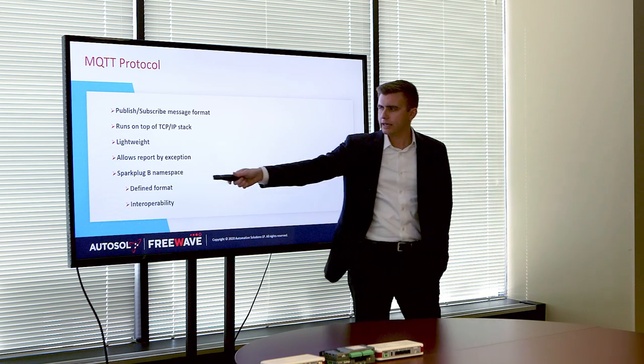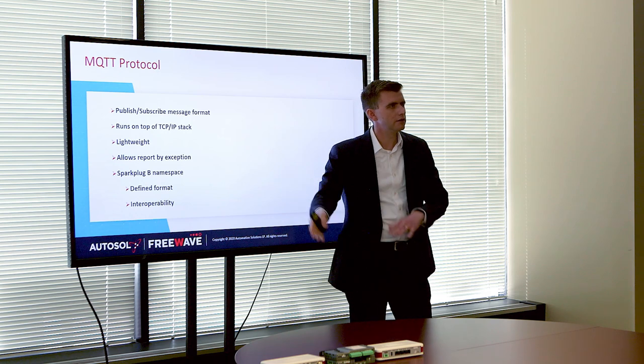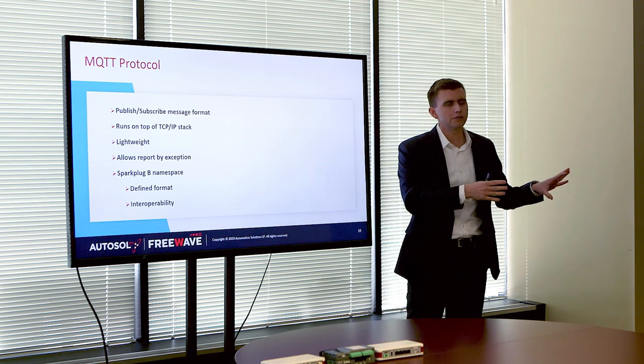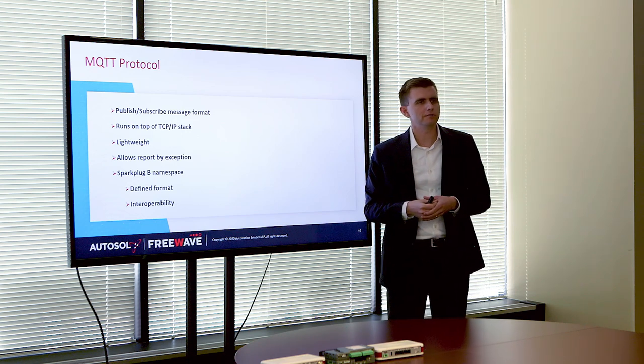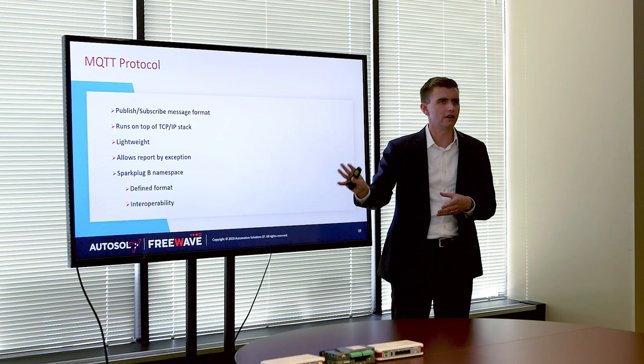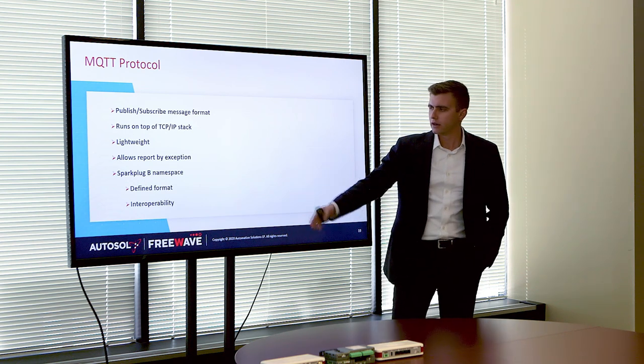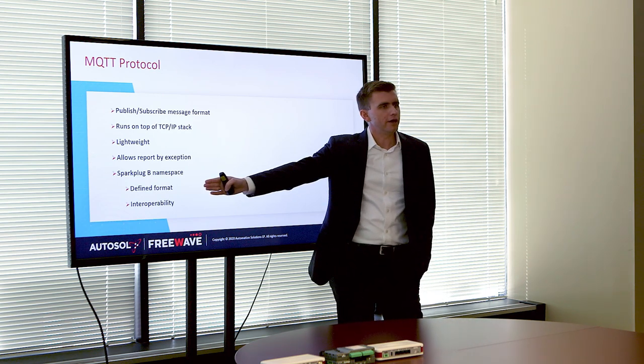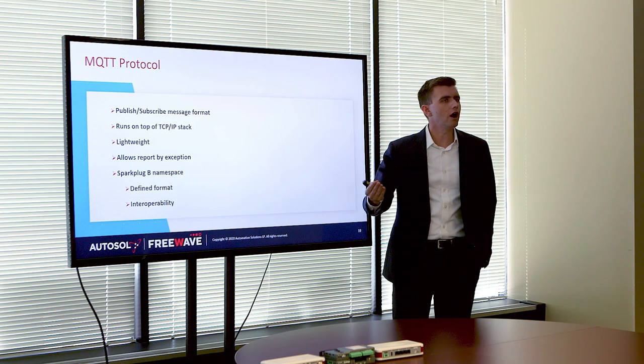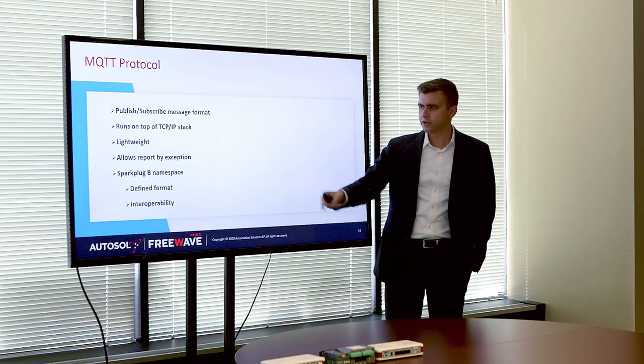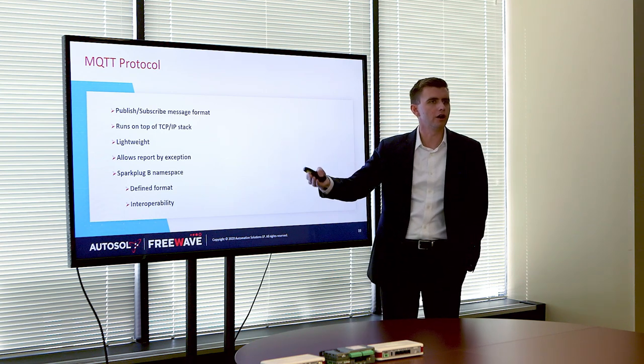MQTT has a namespace called SparkplugB. There's plain MQTT and then there's MQTT SparkplugB — the difference being there is no standard namespace for MQTT. Just because someone has MQTT doesn't mean their JSON message format will work with another piece of software. But if I say I follow the SparkplugB namespace and I want to connect to something like PI which also follows that namespace, we are going to be interoperable out of the box. This standard has really helped the adoption of MQTT into a broader part of our business.